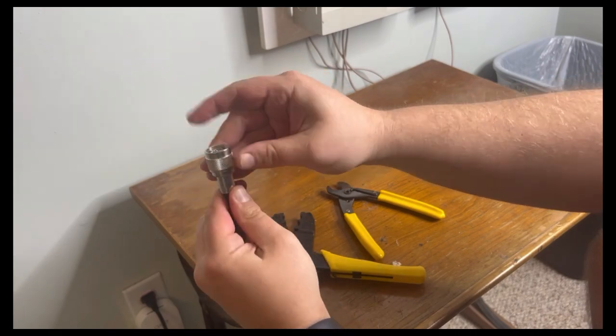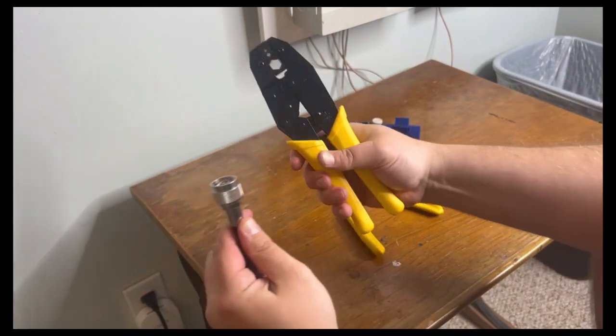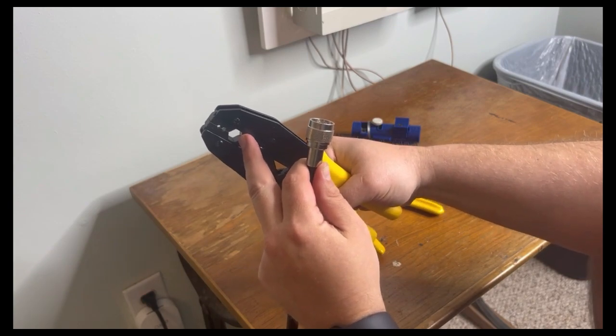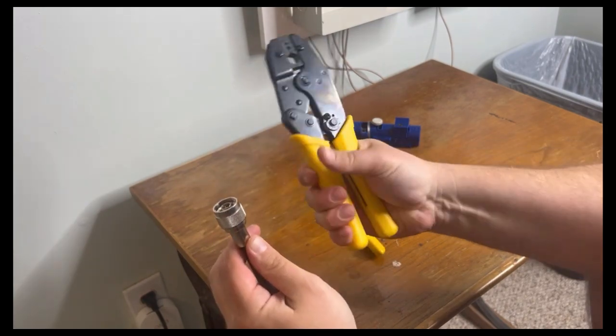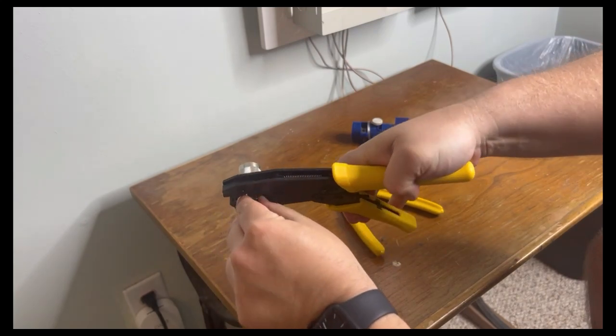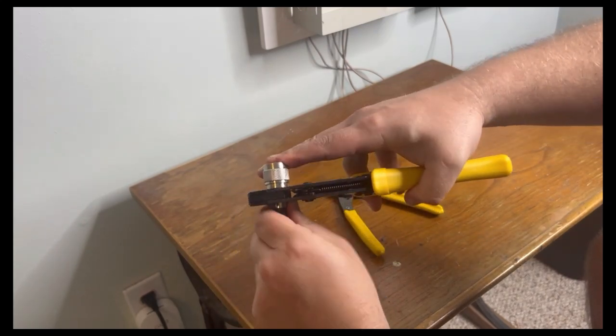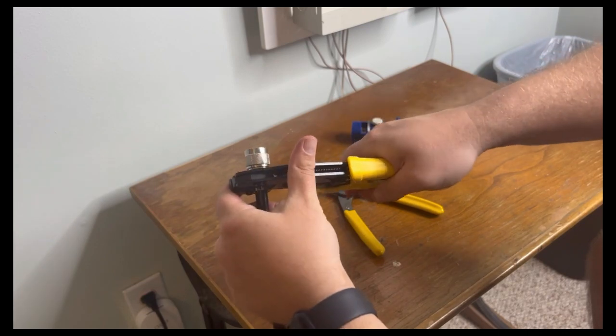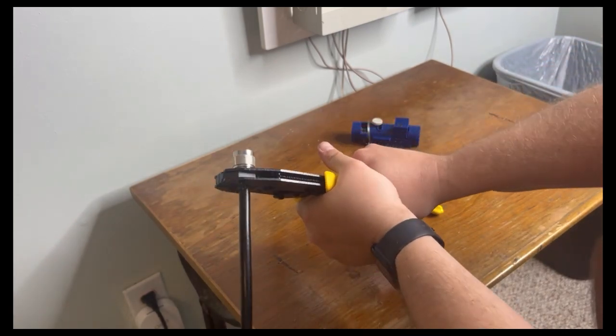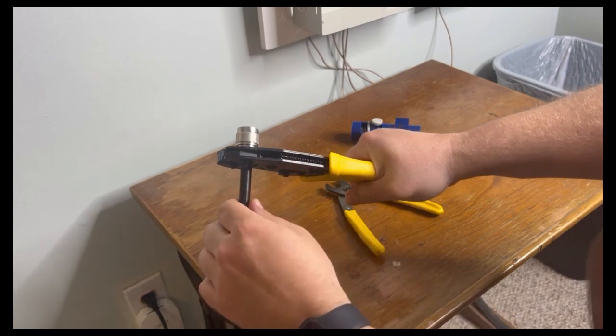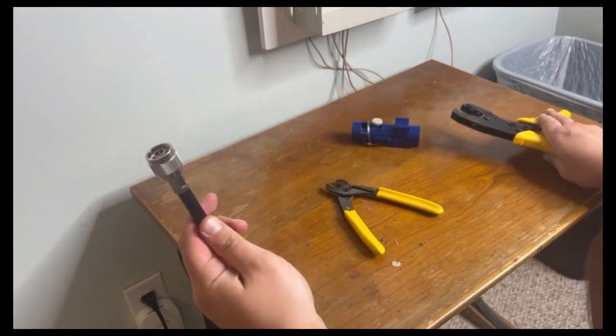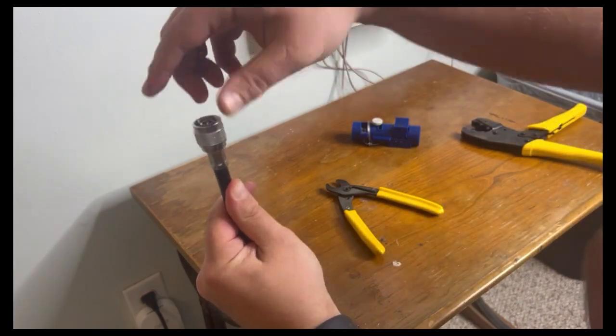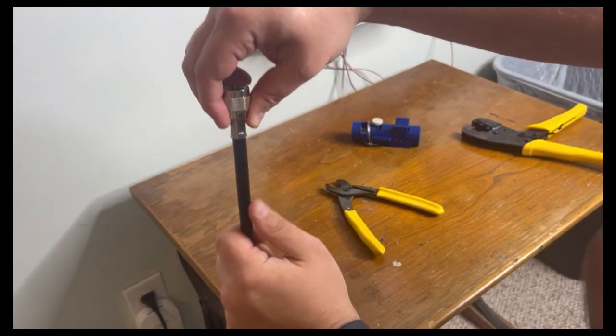We're going to use the largest holes in our crimper. Go as close to the base as possible, then squeeze until it releases. This can be a little hard depending on the tool. And there we go - we have a perfectly applied connector.